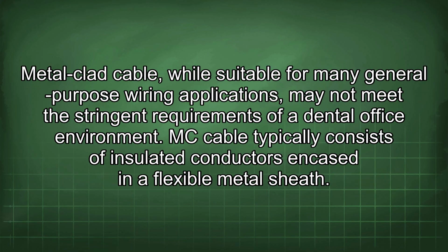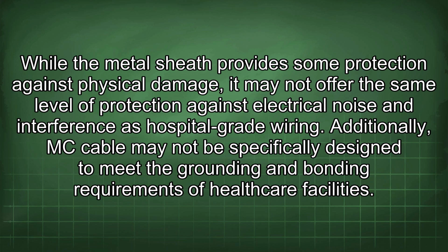Metal-clad cable, while suitable for many general-purpose wiring applications, may not meet the stringent requirements of a dental office environment. MC cable typically consists of insulated conductors encased in a flexible metal sheath. While the metal sheath provides some protection against physical damage, it may not offer the same level of protection against electrical noise and interference as hospital-grade wiring. Additionally, MC cable may not be specifically designed to meet the grounding and bonding requirements of healthcare facilities.